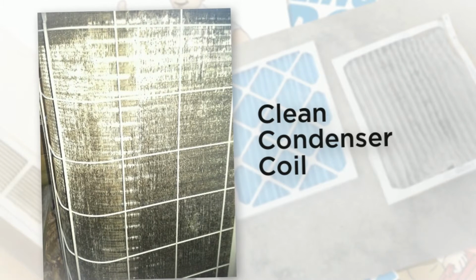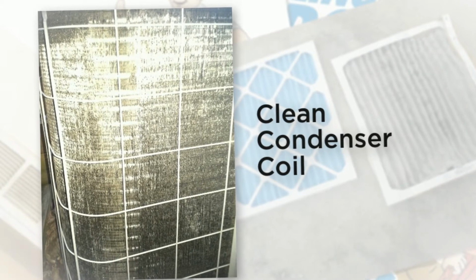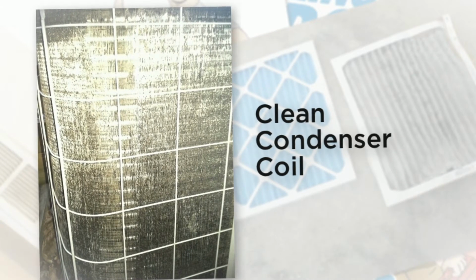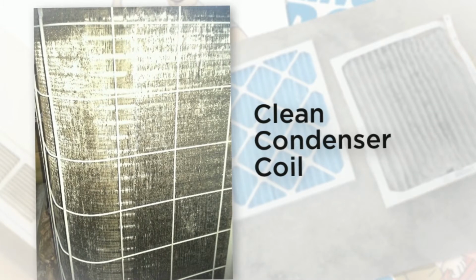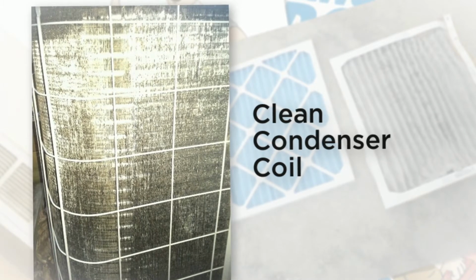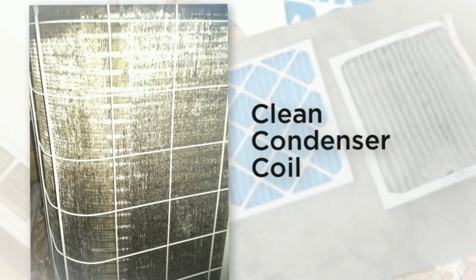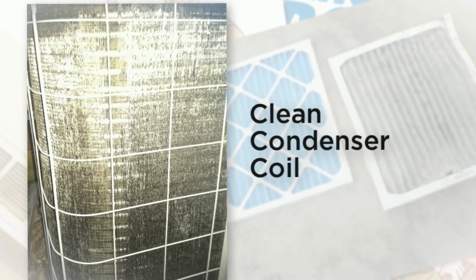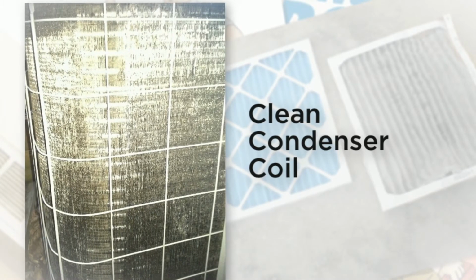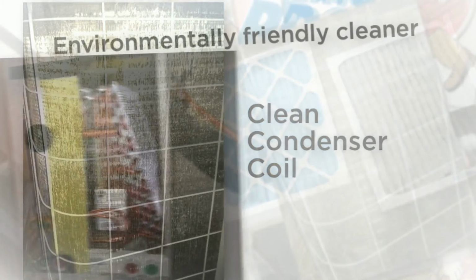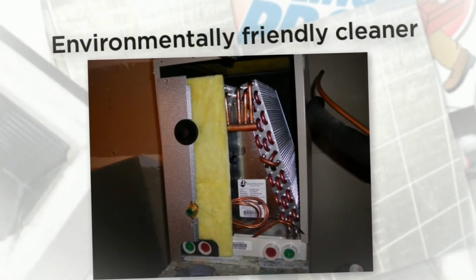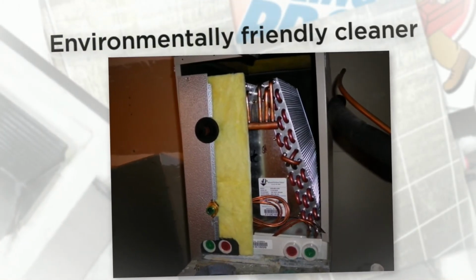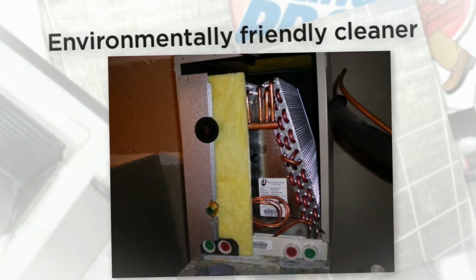Second, clean the condenser coil at least once per year and always after cutting the grass around the air conditioner. The condenser coil is located within the air conditioner cabinet surrounding the unit. This can be accomplished with a water hose. Never use a pressure washer, it'll damage the coil fins. If the coil is very dirty, a chemical cleaning will be required.